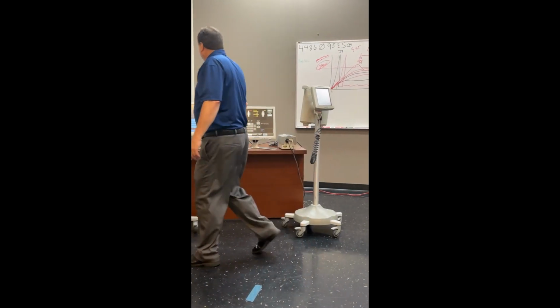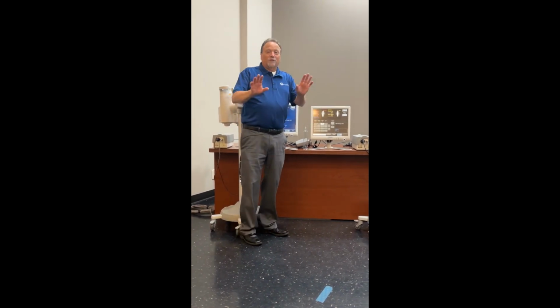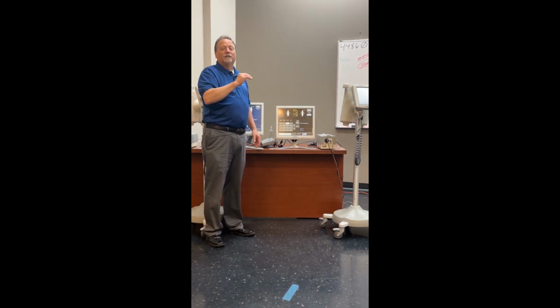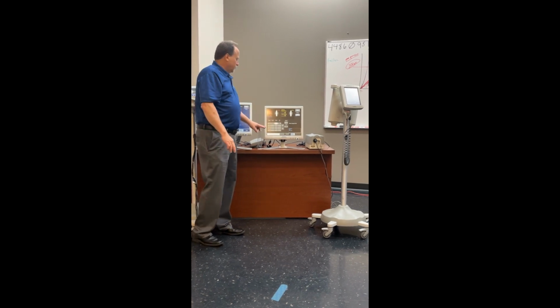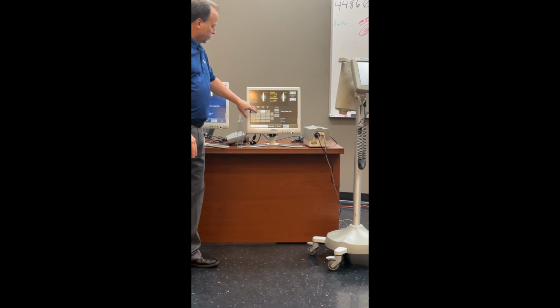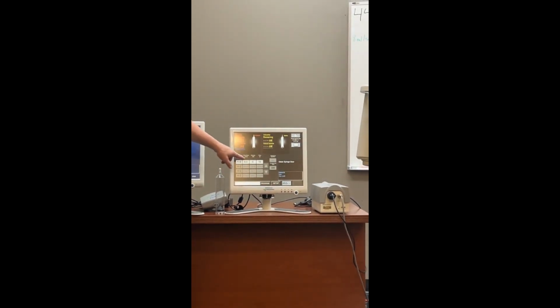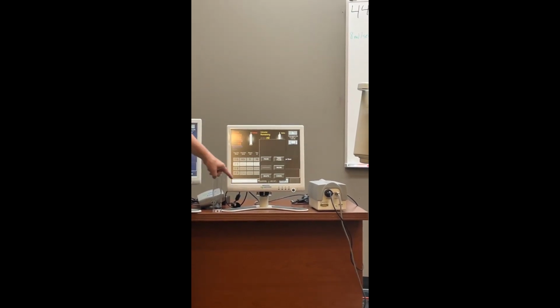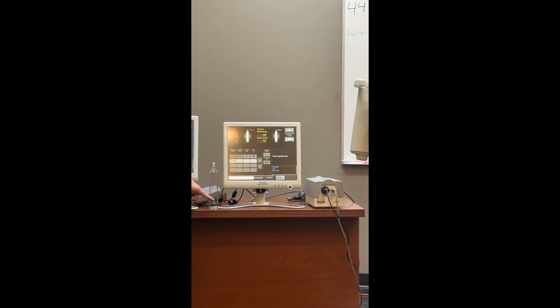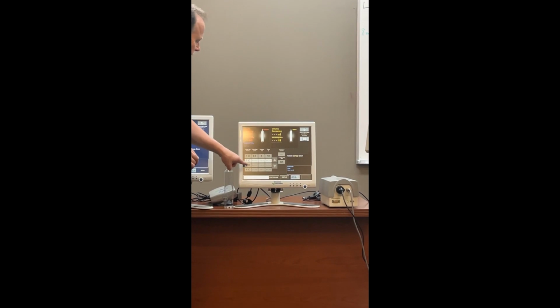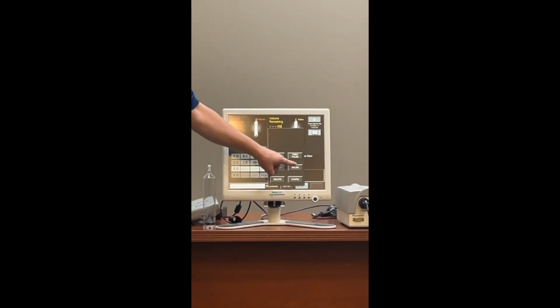So let's look at entering a protocol. If you've dealt with a Stellant, you know you can go contrast, saline, and so on. With these injectors, if you go to select one for contrast, it automatically goes to contrast. You can't start with saline. It goes straight to contrast. That's your first phase. I put 0.5, 5, and 10 in there. The second phase is already listed as contrast. If you select saline, all the other phases are wiped out. Once you hit saline, you can't add any more phases. But if you hit contrast, and let's do a 10, well, that would be a 1. And then the fourth phase is blanked out after the third phase of saline.